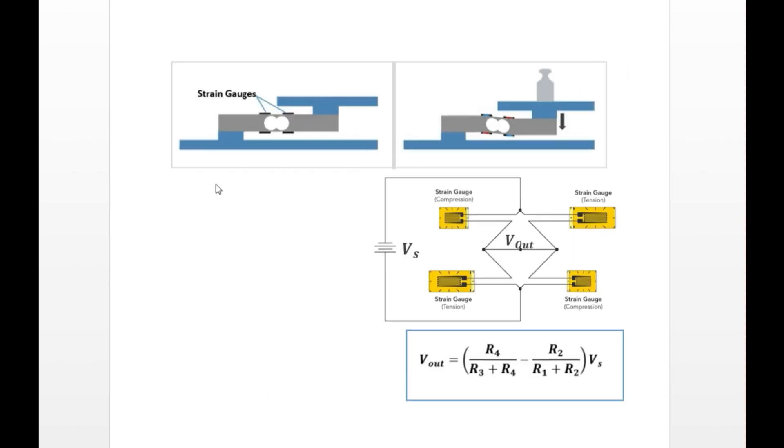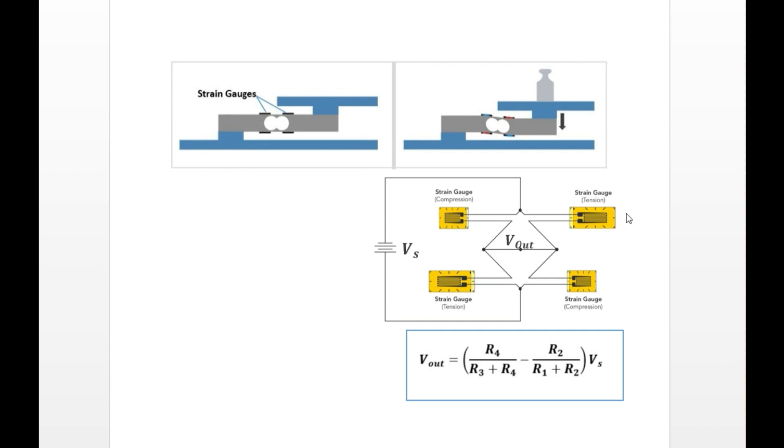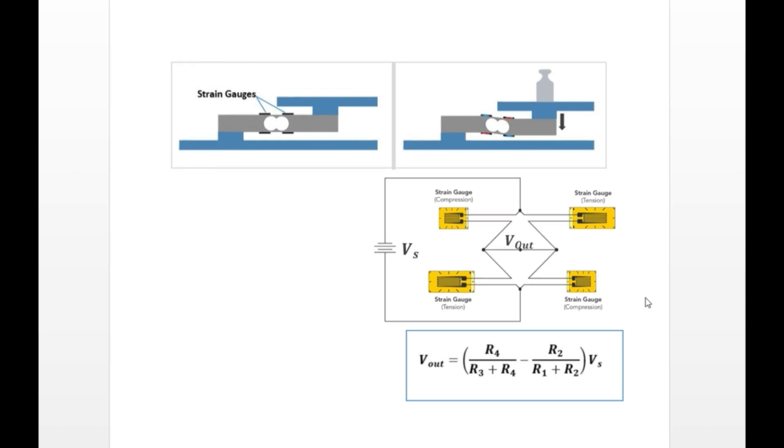That same principle can be used when setting up your bar type load cell. When setting up this type of load cell, you should leave enough room for the load cell to bend when subject to force. So one end of the load cell will be fixed, and the other end will be left suspended with a platform where you are going to be placing your weight. So whenever you apply a force or a weight on the load cell, it will undergo some kind of bending or deformation. Therefore, some of the strain gauges will undergo compression, and others will undergo tension forces. And because of this, they are going to have a change in resistance. So whenever there is a change in resistance in the arms of the Wheatstone bridge, that means there is going to be a voltage difference. Therefore, there is going to be an output voltage which can be calculated using the equation I have already shown you for the working of the Wheatstone bridge. So in simple terms, that's how our four-wire bar type strain gauge load cell works.